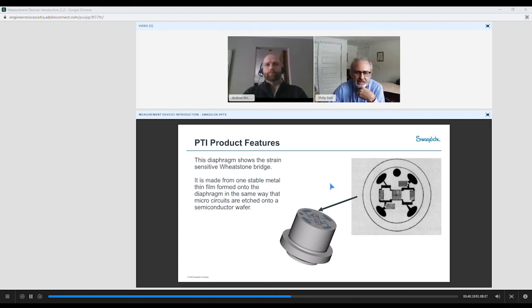Wheatstone invented that back in the 1800s. And really what you're doing, the shortest answer I can give you, is comparing a known to an unknown. Like a strain gauge, as we apply pressure to this thin film, it changes the resistance of the circuit, of that printed circuit. It's like a semiconductor wafer, and it compares the two and converts that into an electronic signal that is sent back.